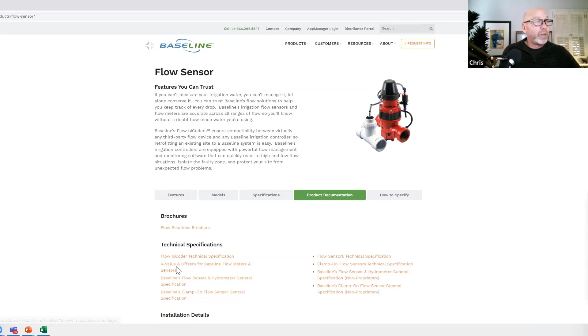It's funny because they actually say Netafim and Bermad, so technically we should go to Netafim and Bermad's websites to get this information. However, since our baseline hydrometer is Netafim, we're bringing you to that page to show where to find it. If you're using a manufacturer's flow sensor other than baseline, you can get the K value from that manufacturer. With a baseline hydrometer, go to the flow sensor products page on the website, under technical specifications, and you'll see a document called K value and offsets for baseline flow meters and sensors. Click that link and it opens a PDF chart listing all the K values and offsets, or pulses per gallon, associated with those different size devices.